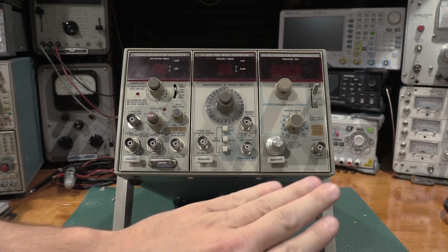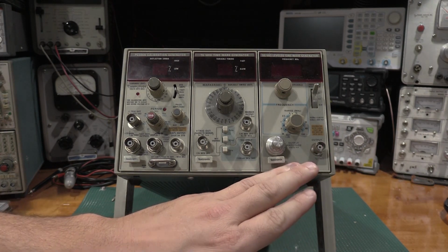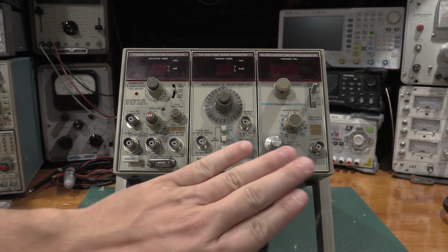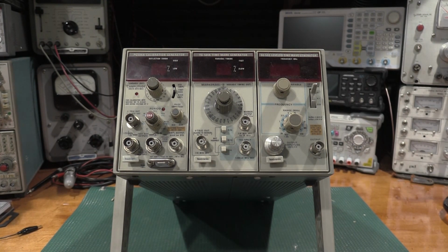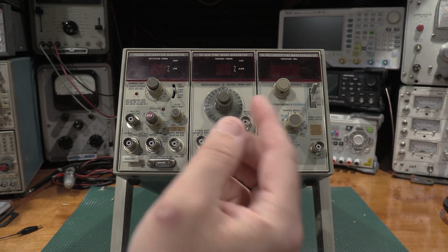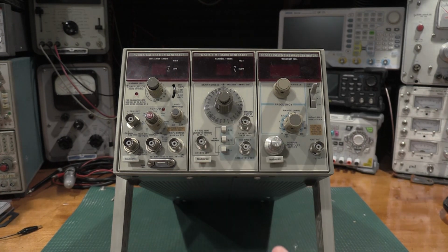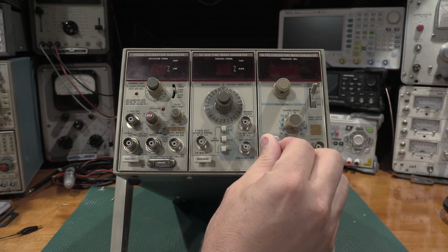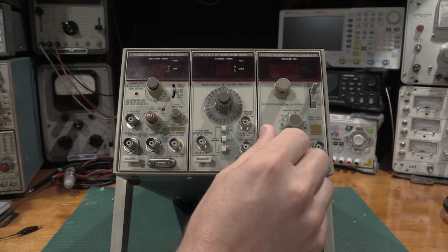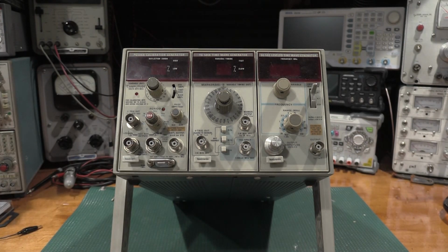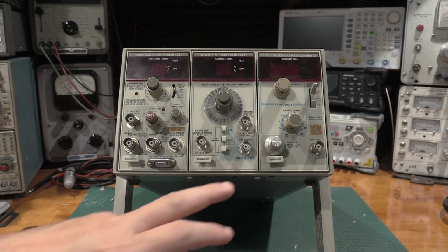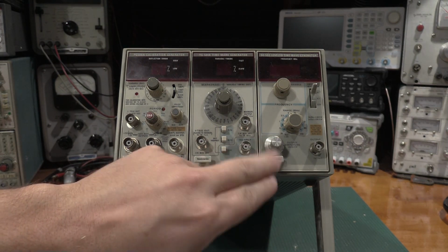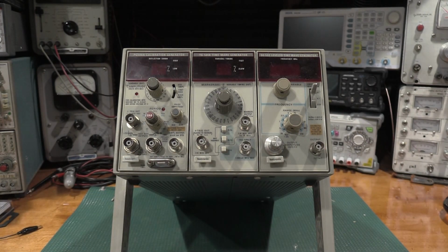So you can use an SG503 without the cable. When using an SG503, if you're doing relative measurements, not exact measurements, and you don't necessarily care what the dial setting is here, you can get away without the super precise cable. It's only when you need to dial in and match what's coming out of the end of the cable that you need the calibrated cable.